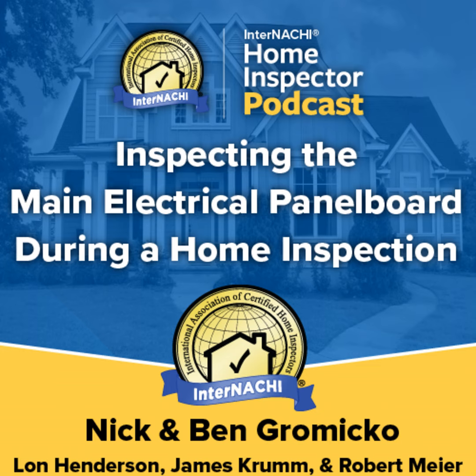Mounting. Panel boards should be mounted as close to where the service entrance cable enters the house as possible. When the panel board is mounted in a basement, the panel board may be observed attached to a piece of plywood. The wood provides a flat, reliable surface for mounting the box and stapling the cables within 12 inches of the box or as the local code requires.